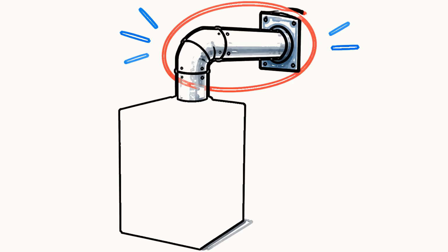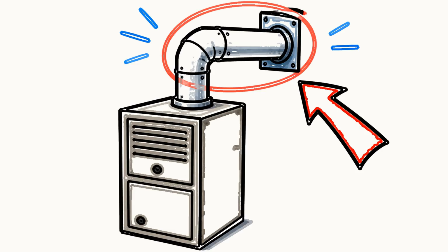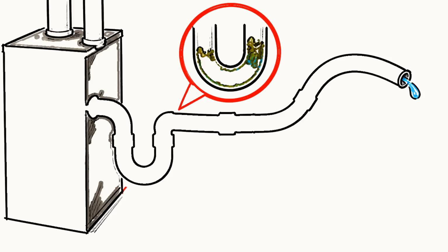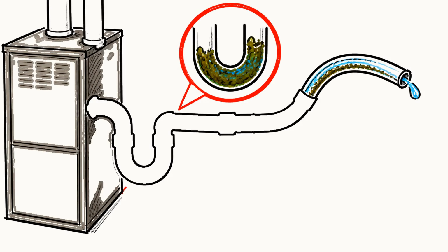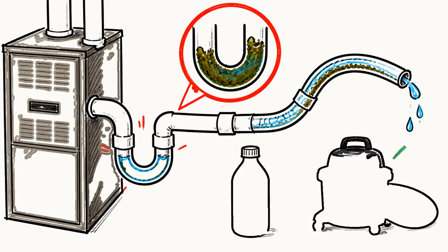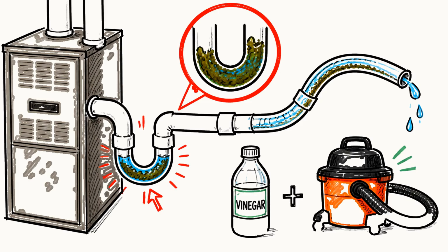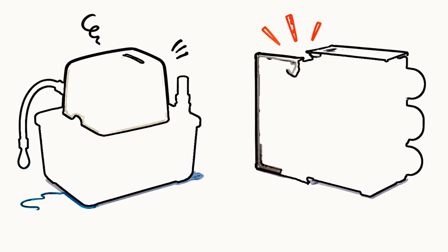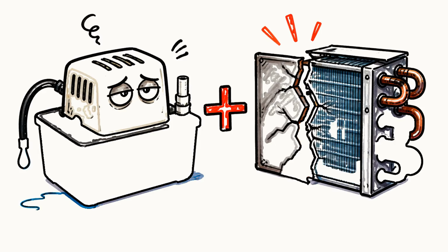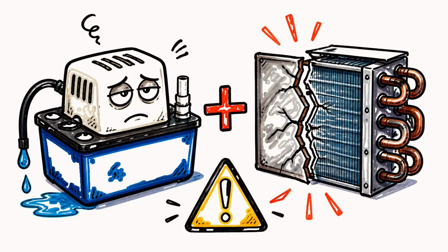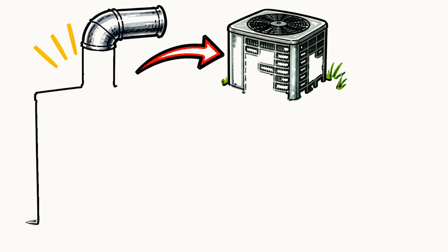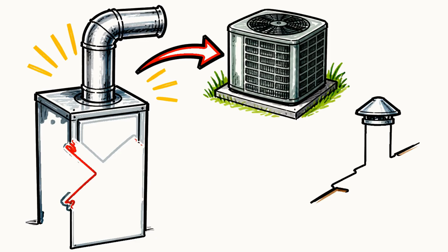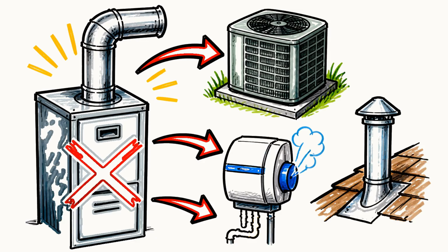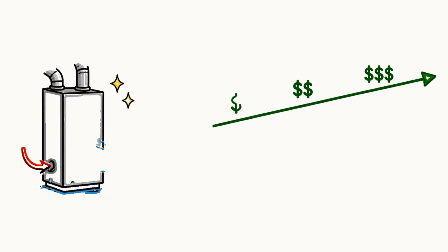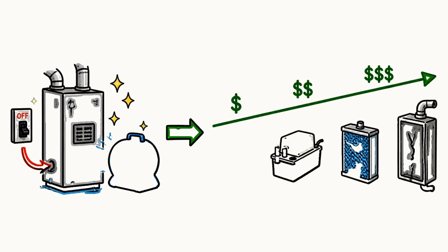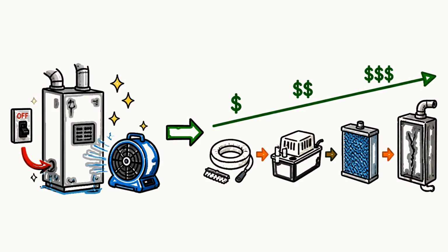So to pull it together, find your exhaust pipe first. White PVC means the furnace makes water on purpose and your leak is in the drain system, which is almost always a clogged trap or hose you can clear yourself with vinegar and a shop vac, sometimes a tired condensate pump, and only rarely a cracked heat exchanger that calls for a pro. A metal pipe means the furnace is not the culprit and you are really looking at the air conditioner, a humidifier, or the venting. Whichever one you have, shut it down, dry it out, and work from the cheap and likely causes toward the expensive and rare ones.